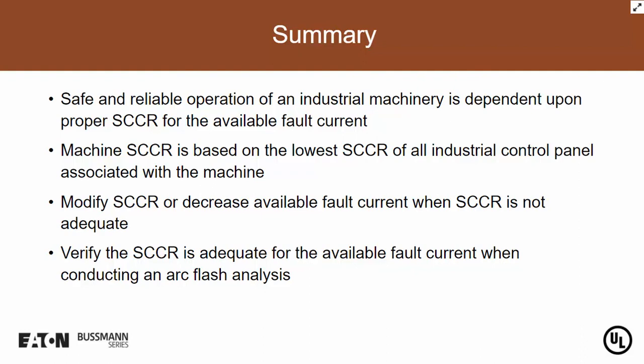And finally, number 4, verify the SCCR is adequate for the available fault current when conducting an arc flash analysis. When we're doing an arc flash analysis, we need to take into account the SCCR of the machines and the industrial control panels and make sure it's adequate. I have seen so many machines where the SCCR may say 5 kA, especially air conditioning units greater than 60 amps. That's when the issue occurs: they're rated for 5 kA, and I see a PPE sticker on that air conditioning unit and the available fault current is 20,000 or 25,000 amps. So we want to make sure the SCCR is adequate for the available fault current, and that we do it when we're doing the arc flash calculation.